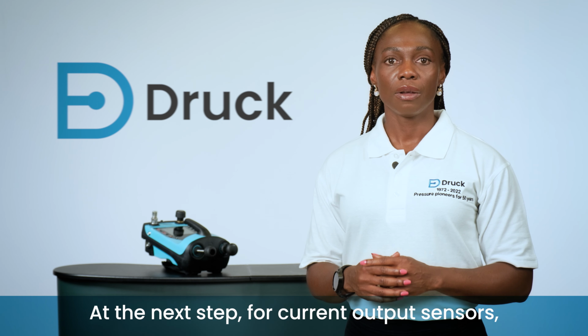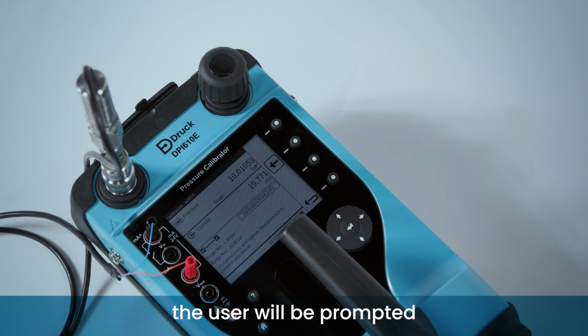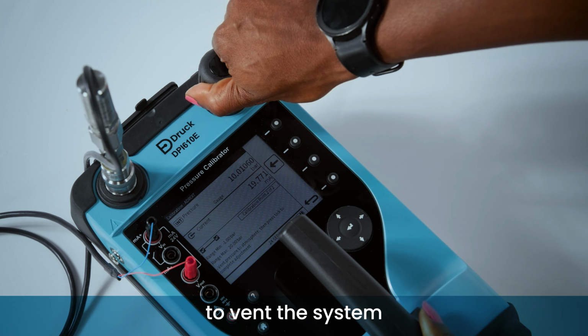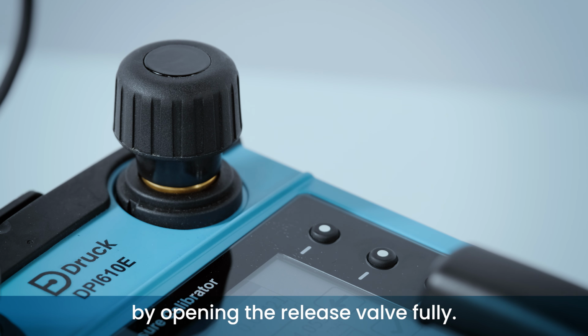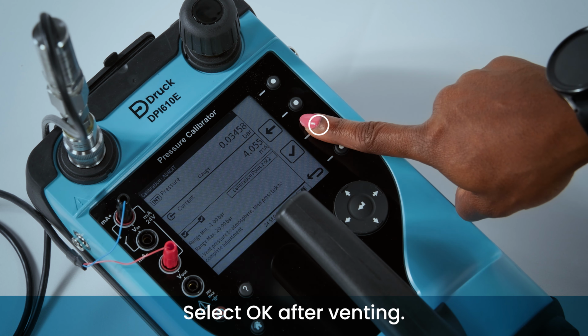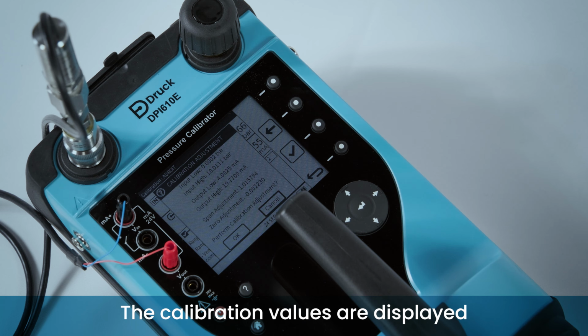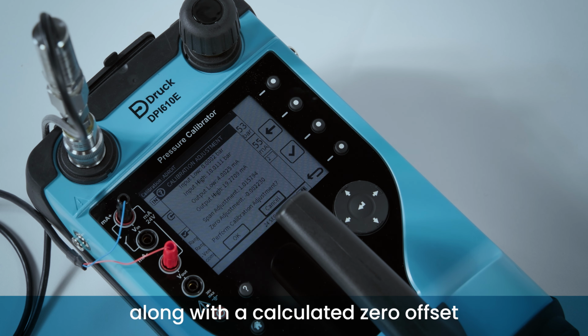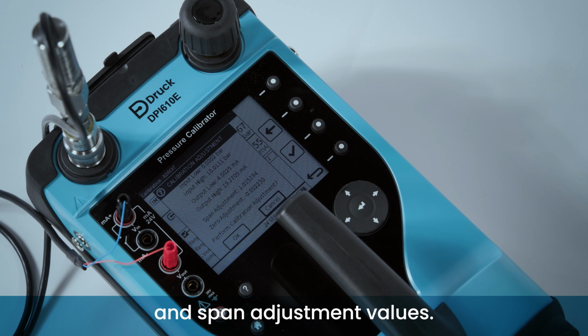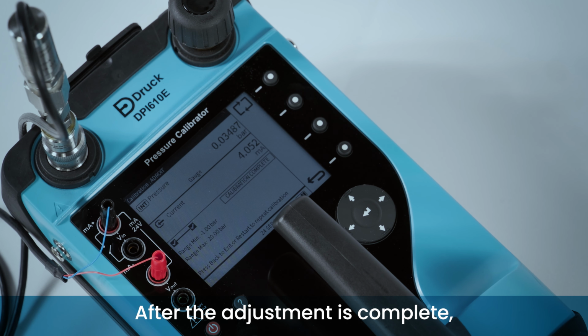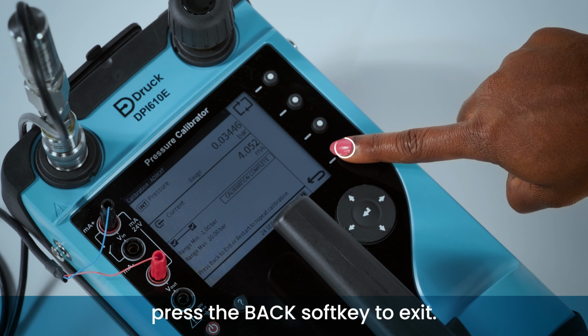At the next step, for current output sensors, the user will be prompted to vent the system by opening the release valve fully. Select OK after venting. The calibration values are displayed along with the calculated zero offset and span adjustment values. Select OK to complete the adjustment. After the adjustment is complete, press the back soft key to exit.